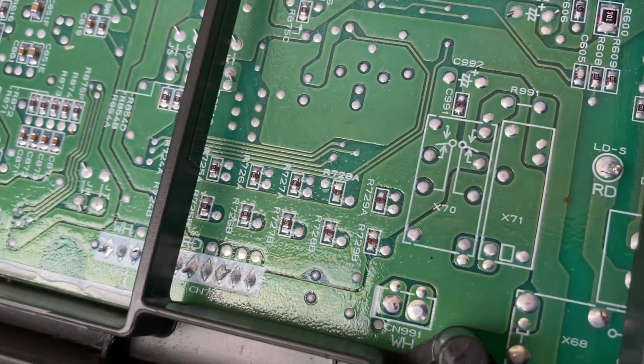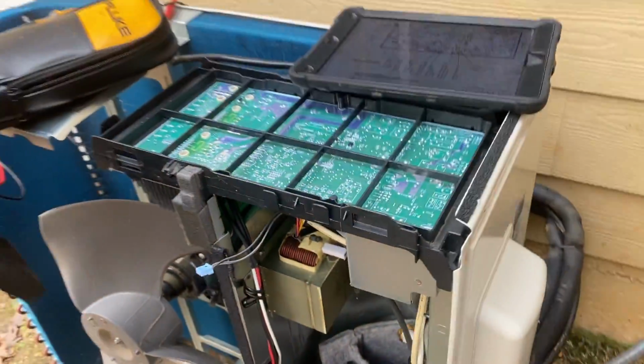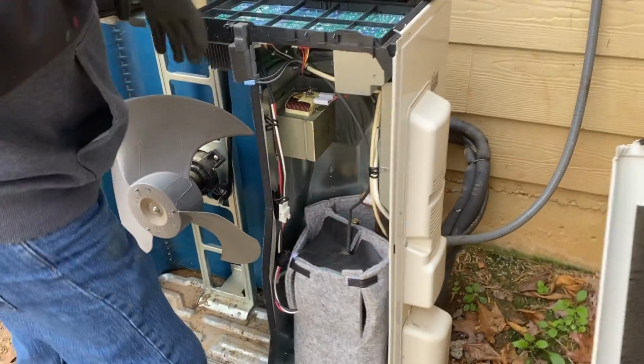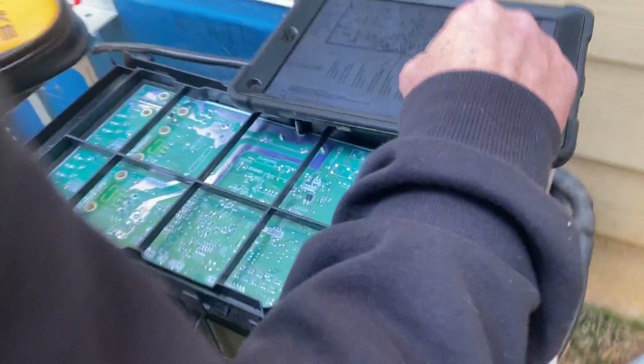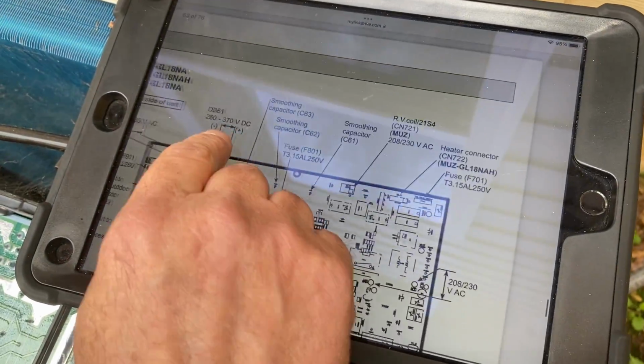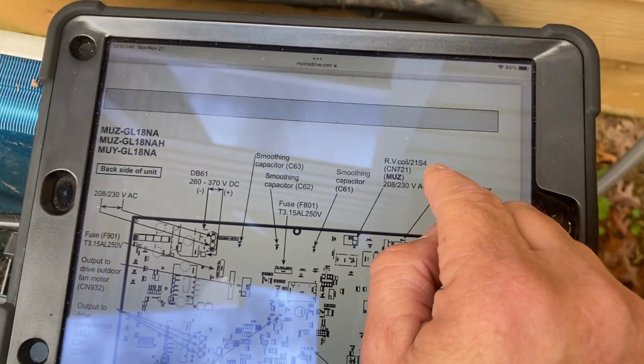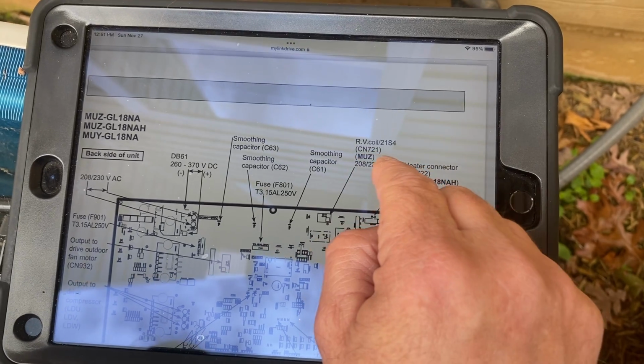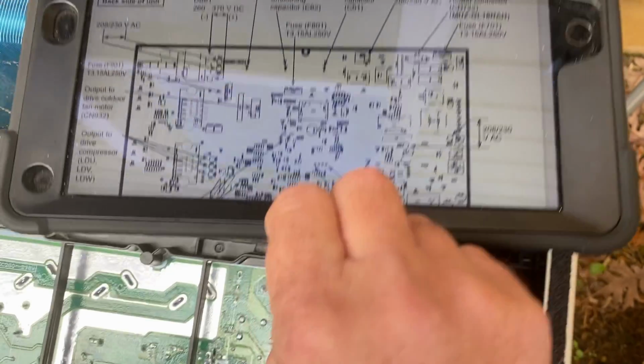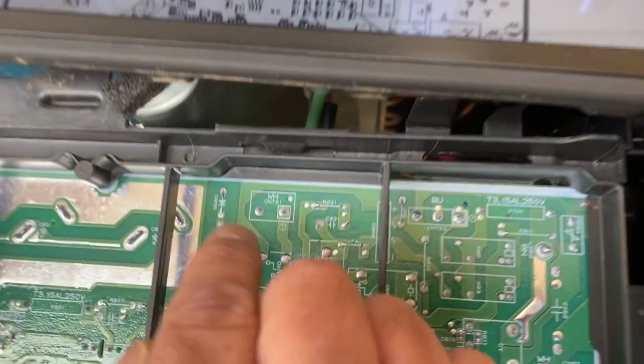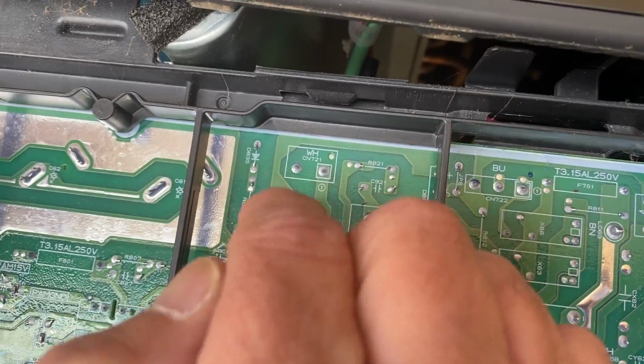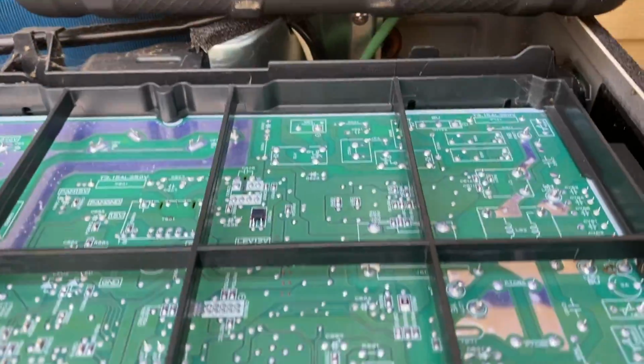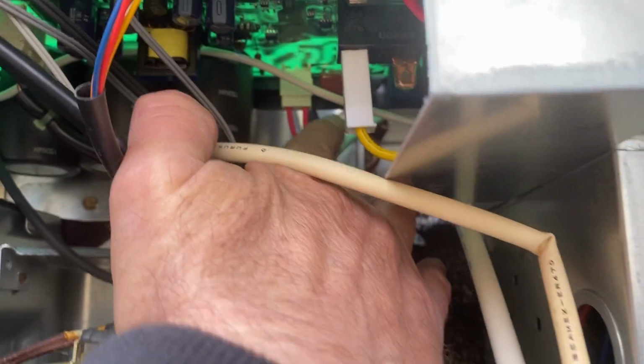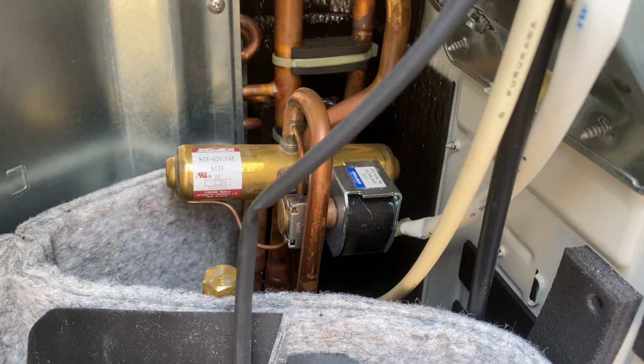If you wanted to know where your reversing valve coil is, you would find it right here. Let's see, where is it at? Right here. The coil 21S4 is CN721, and so you would find it right here. We come over here, CN721, we would know it was right there. So we would just come all the way back to the back here. It was those two pink wires right there, your CN721, and you follow it down, that would be your reversing valve.